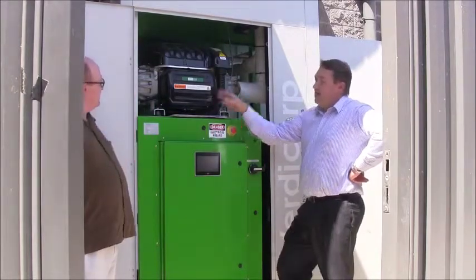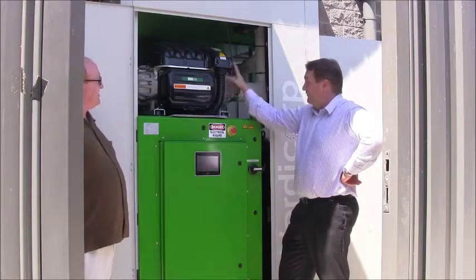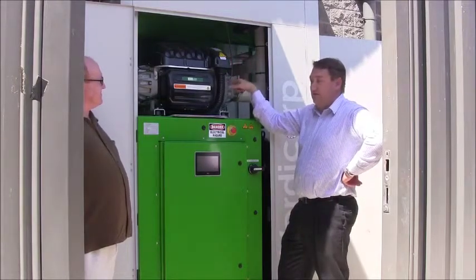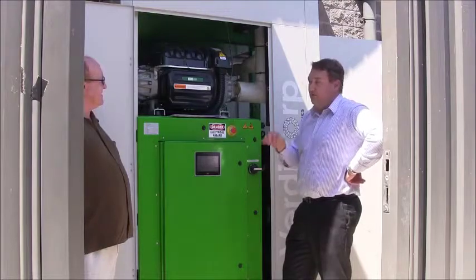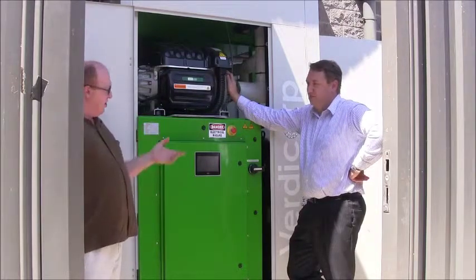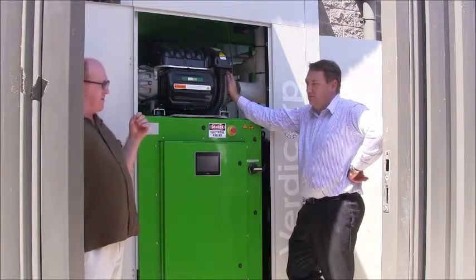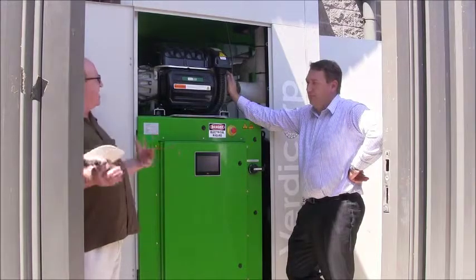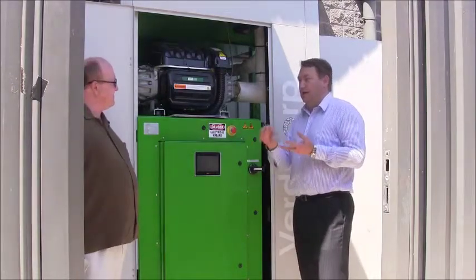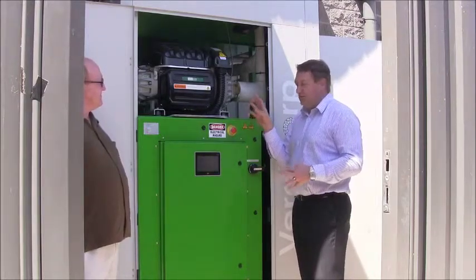This unit is rated at 30 kilowatts. We can change the nozzle and some of the electronics, and this machine can actually make 110 kilowatts as it stands — we just don't have the heat available on this site to do that. Talking about the source of heat: you can use hot oil, jacket water, hot water, hot air, exhaust air from furnaces, from diesel gensets — there's a range of capabilities. We can take steam, pressurised hot water, thermal oil, glycol — a number of different heat sources. We can actually take two different temperatures of heat source in, which is a unique feature of this machine.